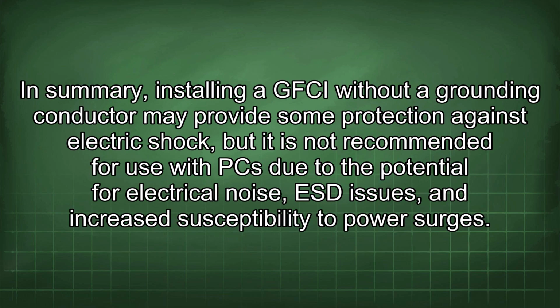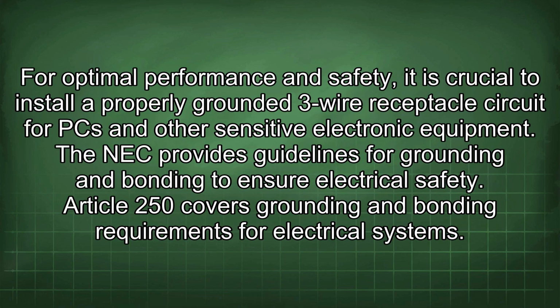In summary, installing a GFCI without a grounding conductor may provide some protection against electric shock, but it is not recommended for use with PC due to the potential for electrical noise, ESD issues, and increased susceptibility to power surges. For optimal performance and safety, it is crucial to install a properly grounded 3-wire receptacle circuit for PC and other sensitive electronic equipment. The NEC provides guidelines for grounding and bonding to ensure electrical safety. Article 250 covers grounding and bonding requirements for electrical systems.